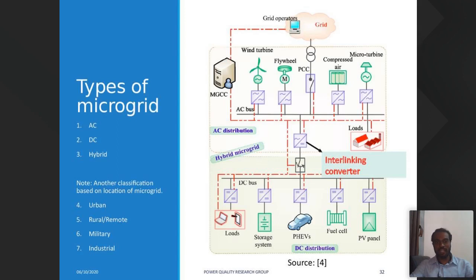If we move on to the types of microgrid, the first classification is based on the type of bus or the type of interconnection we usually have with the load. It's either DC or AC, or it can even be a hybrid microgrid. Here I have shown a hybrid microgrid with AC as well as DC subsystems, where people are preferring DC to reduce the extra power conversion from DC to AC for most renewable energy generation or energy storage systems, leaving out flywheel or variable speed wind energy. So solar, all the battery energy storage systems, and fuel cells generate DC. So people are going for a dual combination of AC bus and DC bus to form a hybrid microgrid.